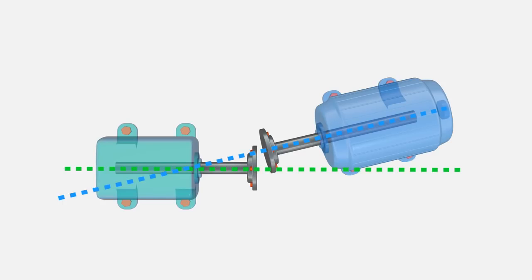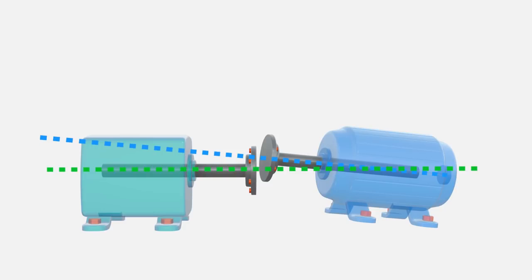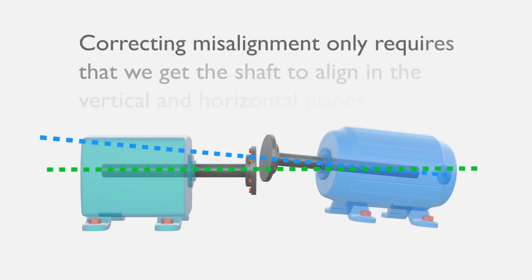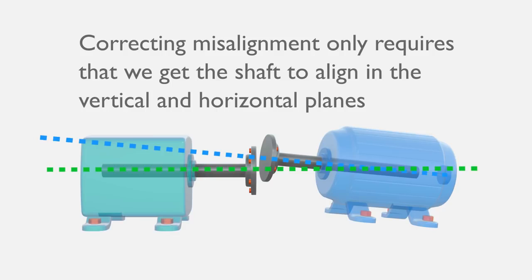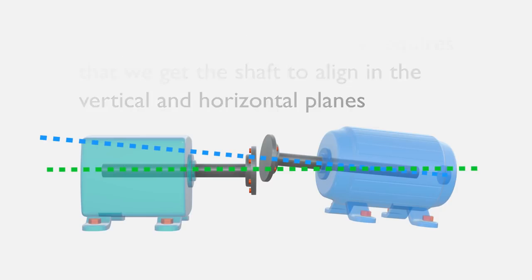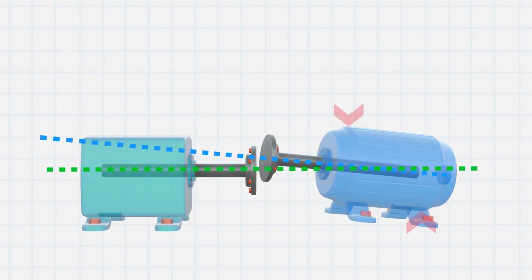While it is much easier to understand misalignment if you can visualize it in three-dimensional space, correcting misalignment only requires that we get the shafts to align in the vertical plane and in the horizontal plane. Fortunately, we are able to adjust the relative position of the two shafts in these two dimensions.